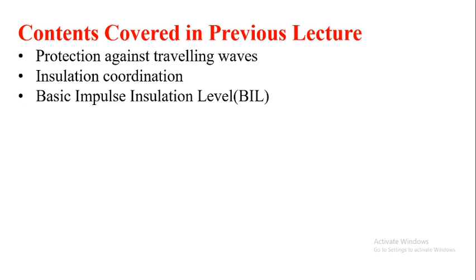Then we also discussed the insulation coordination, which is the coordination between the insulation level of the equipment to be protected and the insulation level of the protective devices. The insulation level of the equipment to be protected should be higher than that of the protective devices. So that we discussed, and also we discussed the basic impulse insulation level. As per the ISI, the standard insulation level will be provided for all the instruments in the power system. So these are the points we discussed in the previous lectures.